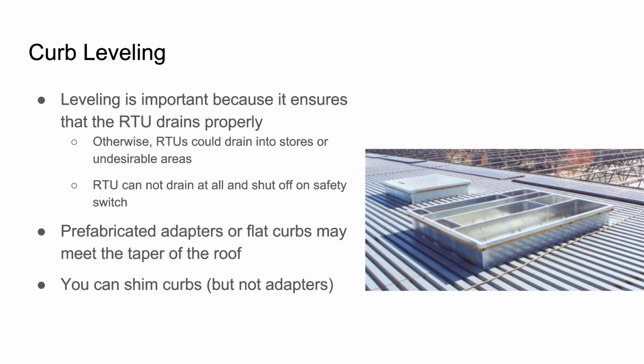Curb leveling we already pretty much talked about—you can shim the curbs, but not the adapters. Leveling is super important; the taller the curb adapter or unit gets, the more important it is, because that compounds the difference. Also, if you're tapering the wrong way and your drain is upstream, there's a possibility you're not tripping your float switch and you're draining right into the store.